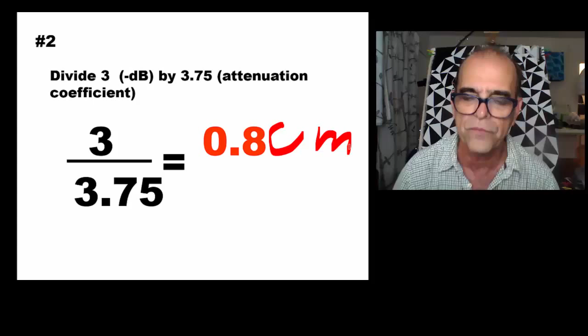We are going to do the same with a high frequency transducer. What is the half value layer thickness of a 7.5 megahertz transducer? Very high frequency transducer. We take 7.5, the frequency, divide by 2, and we get the attenuation coefficient. We divide 3 decibels by the attenuation coefficient and it gives me 0.8 centimeters. In other words, a transducer of 7.5 megahertz needs less than 1 centimeter to be attenuated by half. Only in 0.8 centimeters is it attenuated to the half.